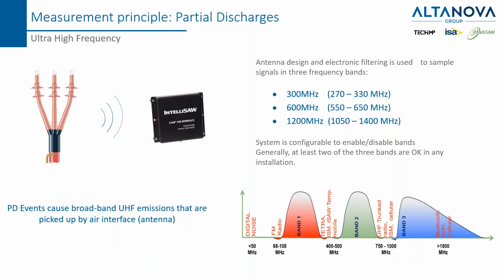Another measurement that the IntelliSAW system is providing is also able to detect the partial discharge coming, for example, from the cable. In fact, the events can cause a broadband UHF emission that is picked up by the air interface. This antenna is designed to receive this signal coming from the PD source in three different bandwidths: 300 megahertz, 600 megahertz, or 1200 megahertz as a central bandwidth.